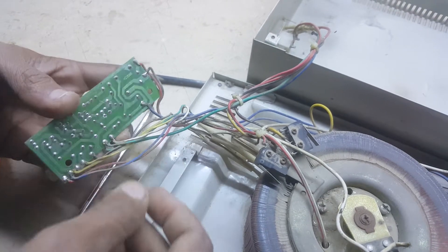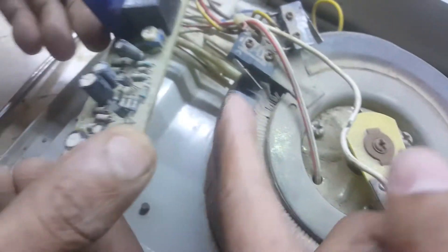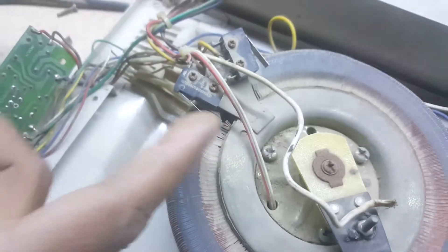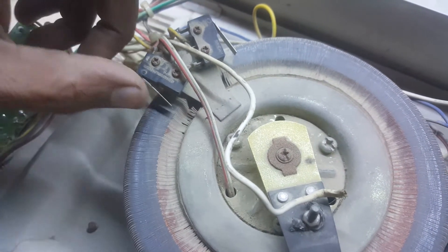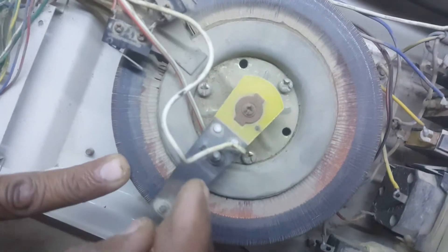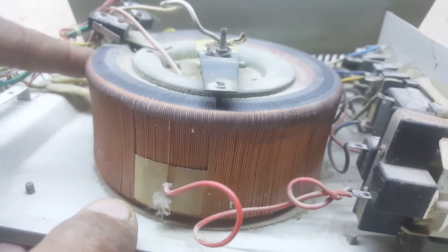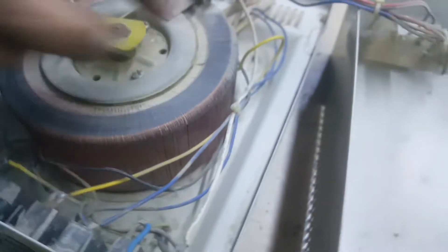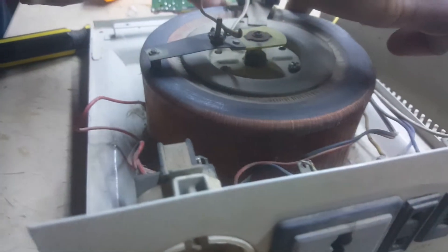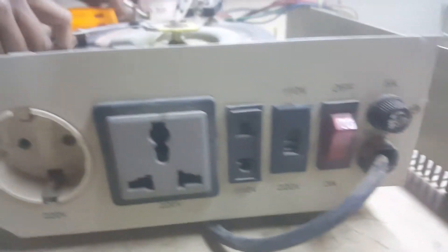The circuit has been open a long time. This is the circuit of this servo motor stabilizer. This is the main circuit to control the servo motor to stabilize output voltage. These buttons are the voltage limit — if voltage increases or decreases out of limit, this will cut off the power. This lever is connected with the sensed voltage. This coil — this square copper coil — works like a regulator from minimum voltage to maximum voltage. It is also available for 110 volt.